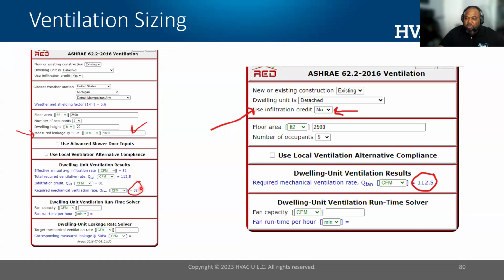So you see it right here, it's 32 because I am using the infiltration credit. All right. If I don't use the infiltration credit and I put in my parameters here, the required fan went from a 32 CFM fan to a 112, 113 CFM fan.